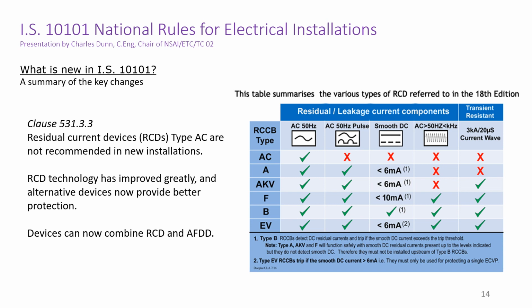Meanwhile, RCD technology has advanced greatly and the electronic sensors are now better tuned to detect earth faults. The problem is that new electronics sometimes impose harmonic waveforms onto the power grid, which can trick or blind the older types of RCDs. New types of RCDs are now on the market, and the older AC type is no longer permitted for new installations. Look at the graphical representation here, and you can see the types of waveform that various RCD types respond to.